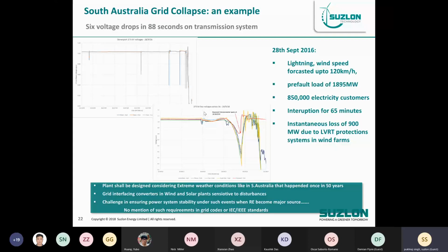And then there was a blackout. South Australia went into blackout, and the grid authority challenged us, asking why our turbine tripped. We said you did not tell us we had to withstand 5, 10, or 20 times in such short durations. How can we plan for it? That's what I was saying - we have to plan and think of such situations while designing the turbines or inverters for such applications. This could really lead to a disaster in some cases.